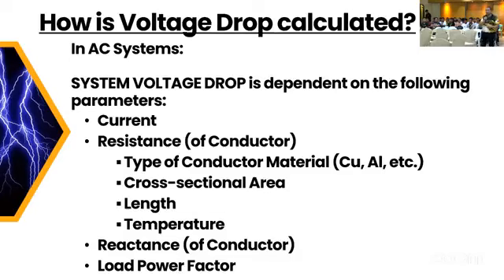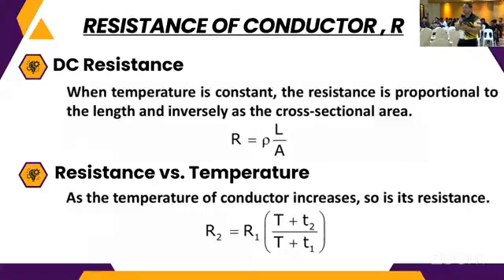Cross-sectional area, length, and the temperature. So when the temperature increases, the resistance increases. So meaning the voltage drop also increases. So from the formula, resistance is equal to resistivity times length over the area. Di ba yung formula natin? If you recall, resistance equals resistivity times length over the cross-sectional area of the conductor. Tama? Okay? Next.